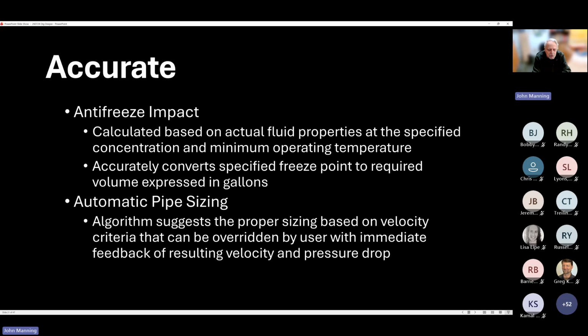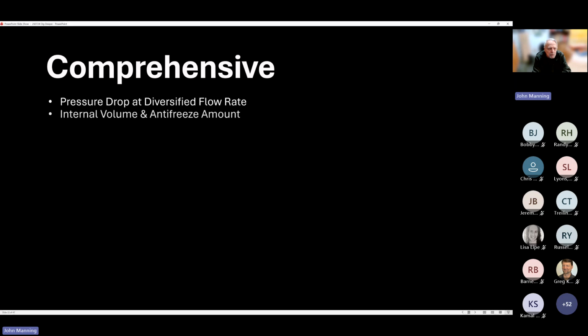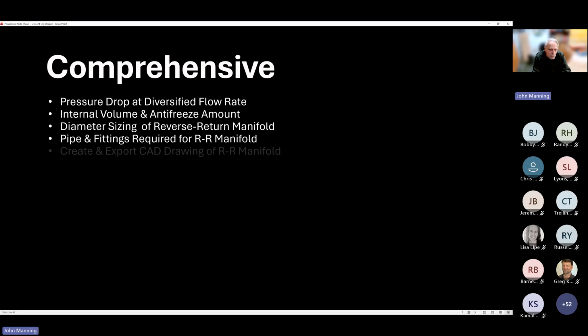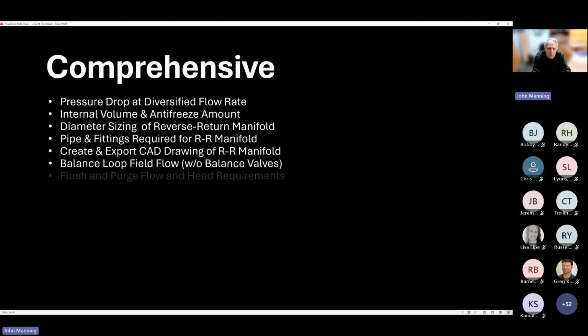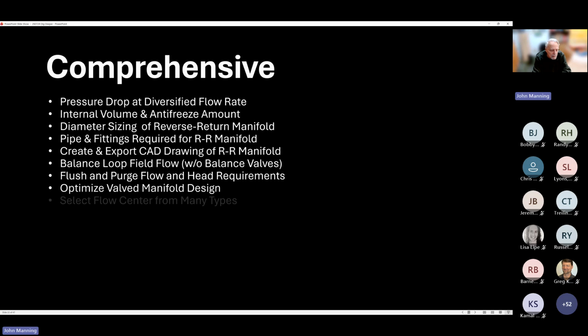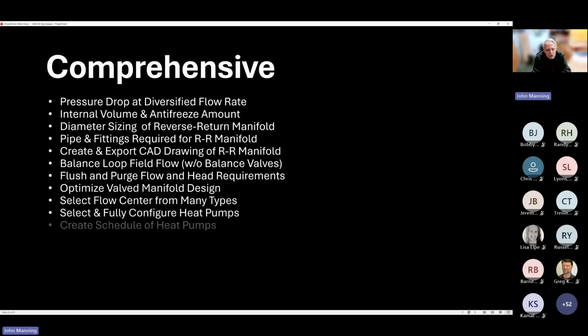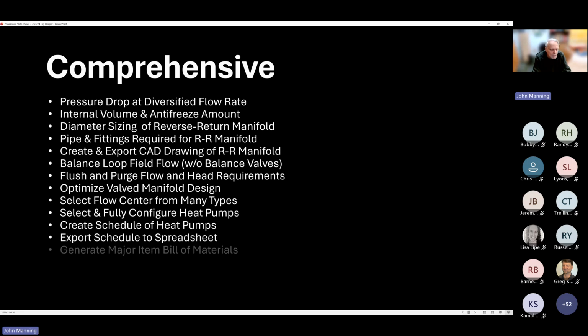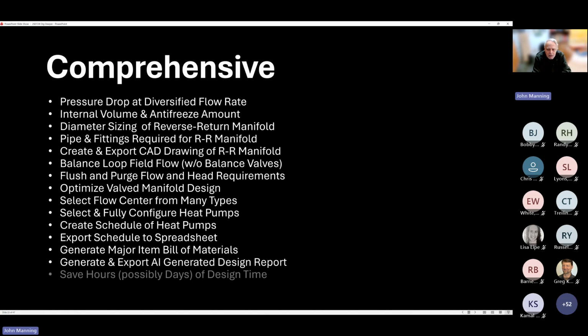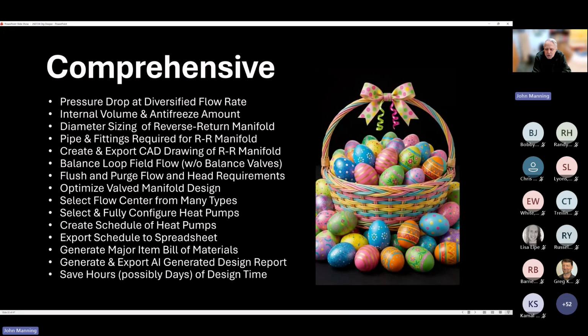Automatic pipe sizing. The program will suggest pipe sizing for diameter, and it's based on the simple velocity. We like to see that above 1.5 feet per second, and that's a starting point for you to select and possibly override those selections. The program is comprehensive. We have so many little tasks that are being performed in the program. And what I'm sharing with you today is really just the tip of the iceberg. All these capabilities are built into the software. I'm going to share some of them with you today, but I really encourage you to sign up for the program, kick the tires, and discover the various Easter eggs that are embedded into the software, which you might find very useful.